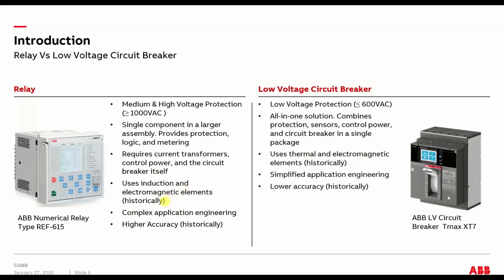A relaying system requires a bunch of engineering, obviously, because you have multiple components and they all have to work together as a system. It's the responsibility of the specifying engineer and design engineer to make sure that the relay, the CTs and the breaker are all working together as a system, and to know what the totality of those components can do performance-wise. Whereas for the low voltage breaker, it's printed in a data sheet exactly what that breaker can do in terms of its curve. The curve includes all the trip and total clear times, so it's a package versus a system.